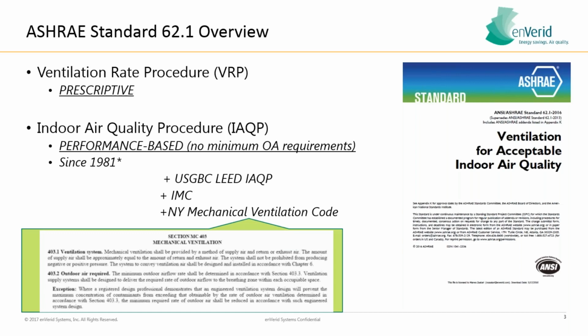The lesser used and relatively unknown, until a few years ago, was the indoor air quality procedure. This has actually been in the standard since before 1981, and it's also referenced in the International Mechanical Code 403, IMC 403, where you can use an engineered system, air cleaning strategies, to reduce the amount of outside air required. And what enVerid does with our engineering partners is we're actually able to reduce outside air in many cases all the way down to just building pressurization.